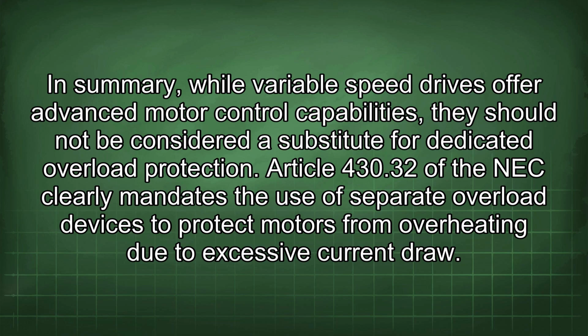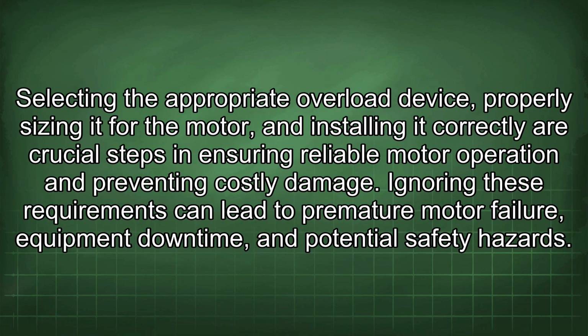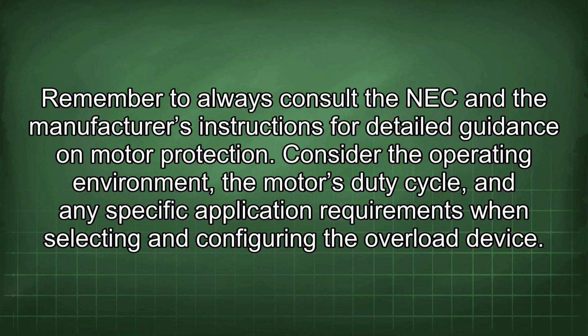430.32 of the NEC clearly mandates the use of separate overload devices to protect motors from overheating due to excessive current draw. Selecting the appropriate overload device, properly sizing it for the motor, and installing it correctly are crucial steps in ensuring reliable motor operation and preventing costly damage. Ignoring these requirements can lead to premature motor failure, equipment downtime, and potential safety hazards. Remember to always consult the NEC and the manufacturer's instructions for detailed guidance on motor protection.